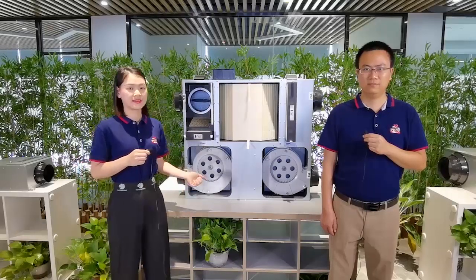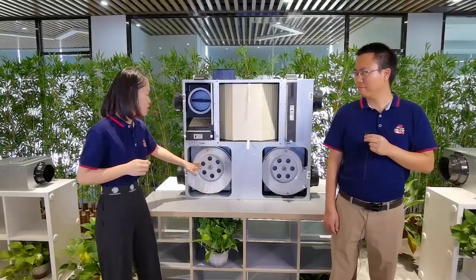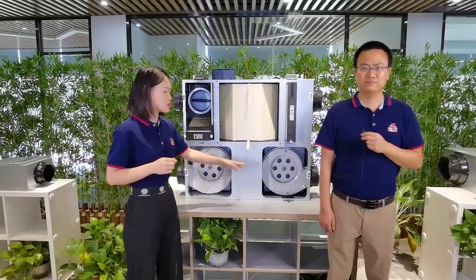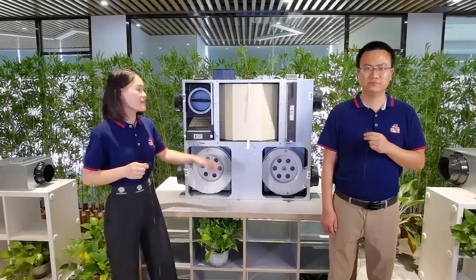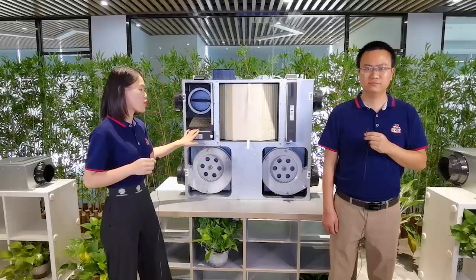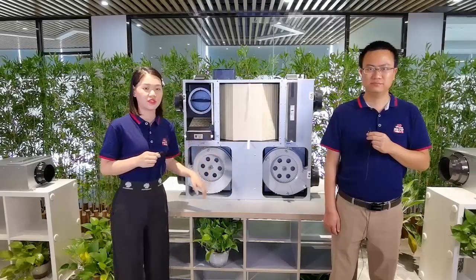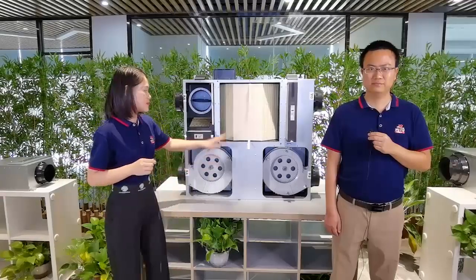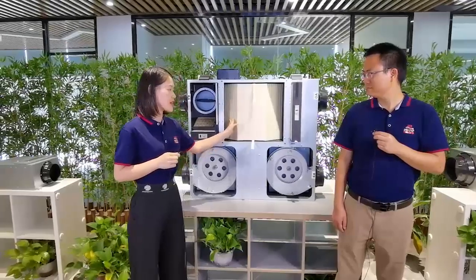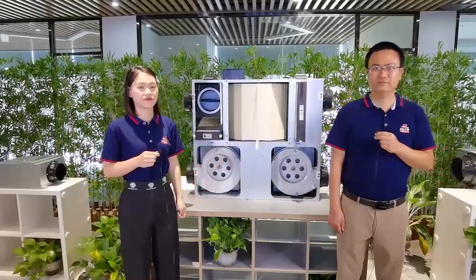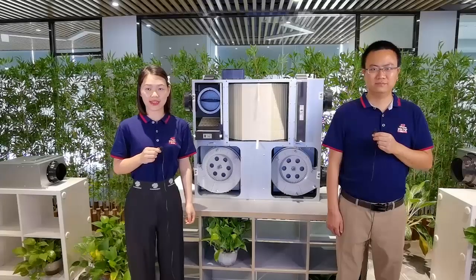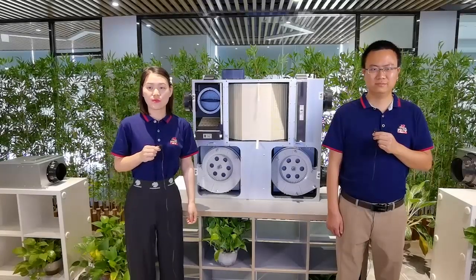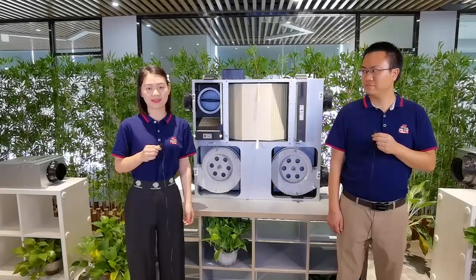You can maintain the parts via the access door at the bottom. These two holes are for the supply fan and exhaust fan maintenance, and these two small holes are for the primary filter and HEPA filter access. The biggest hole is for the cross-flow heat exchanger. You can just open the access door for much easier maintenance. But please remember to cut off the power before carrying out maintenance.